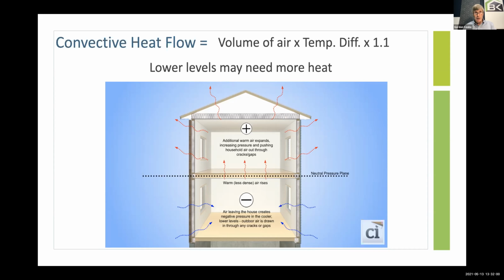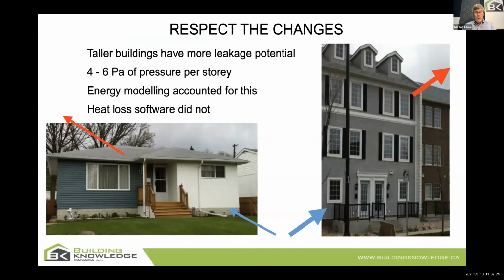And you'll notice there the line, the neutral pressure plane. Of course, this changes on a day-to-day basis because now the wind is blowing, or now you turned on a fan. And this is by no means static. So the algorithms have to assume what? Well, they assume a cold winter's day, they assume it's night, and they assume in this case there's not a lot of wind impacting because they want to do the stack effect. So this is an important one.